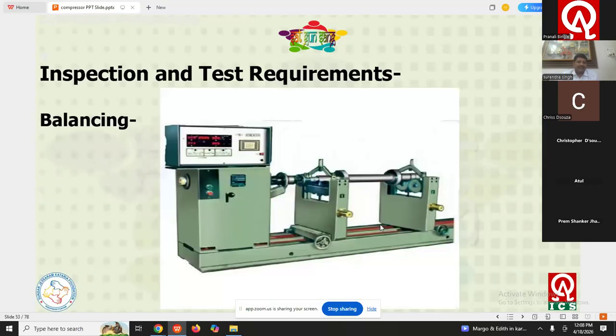This is a balancing setup. You can see this is a balancing machine. This is a display panel. This is the coupling, and this is the test piece. This is the rotor. When we are going to check the unbalanced material, first we need to place this rotor, this rotating part of the compressor, on the rollers. These are the rollers on one side, and this is the second side rollers. So we need to place this rotating part here.